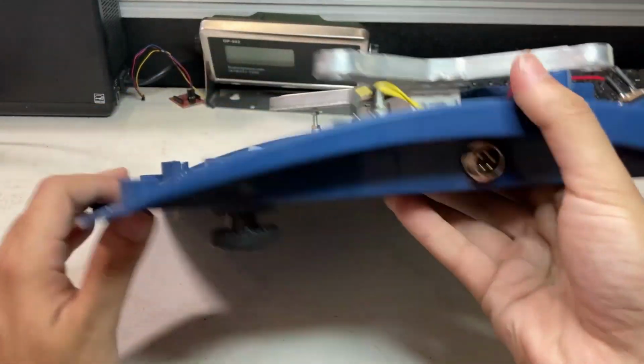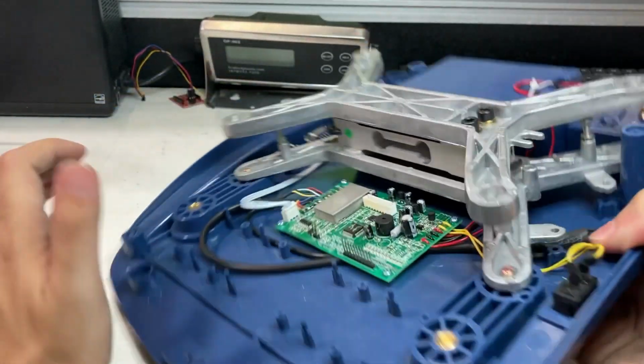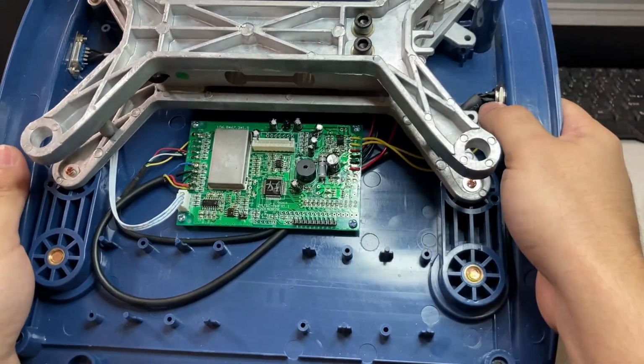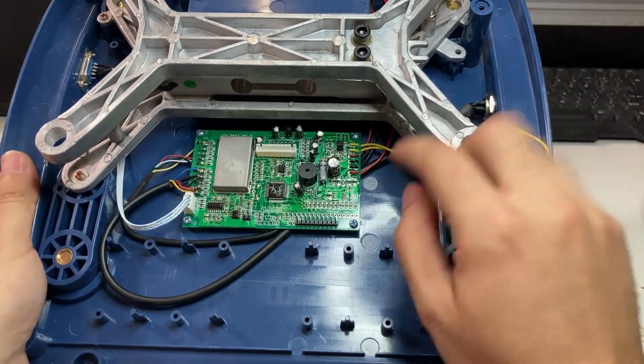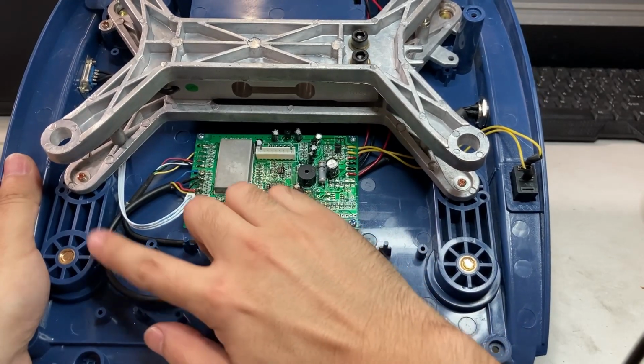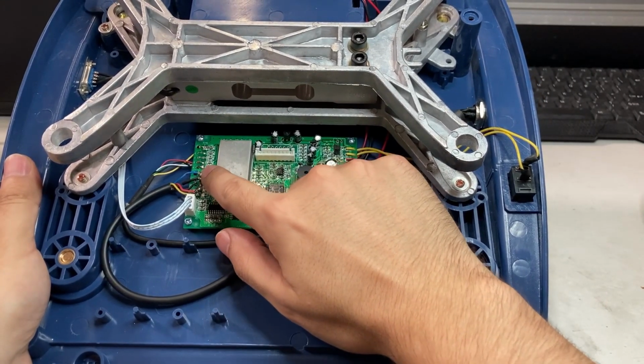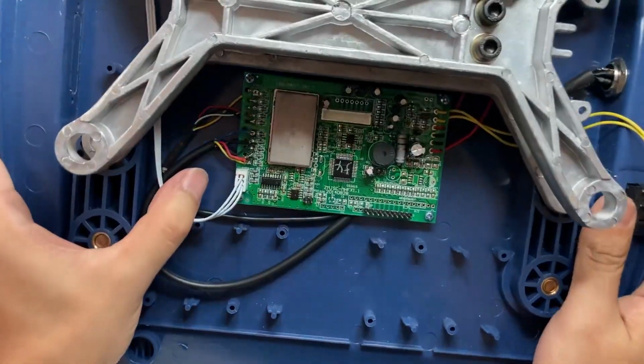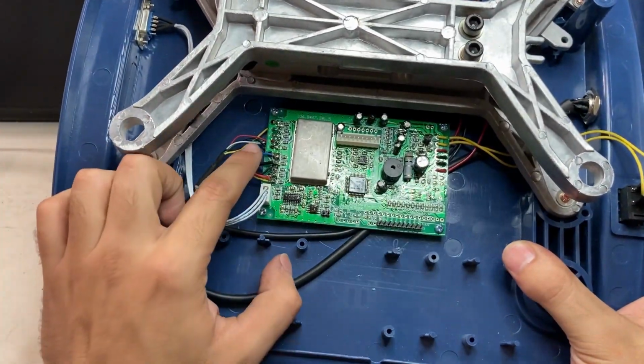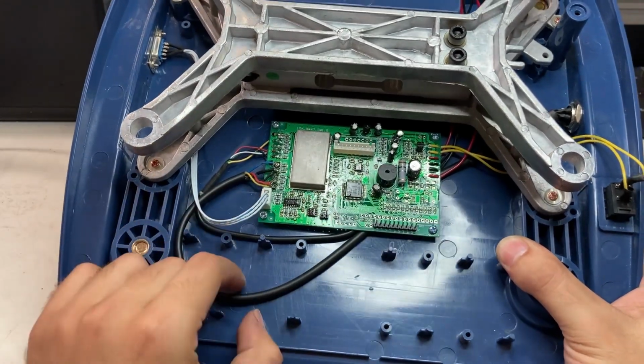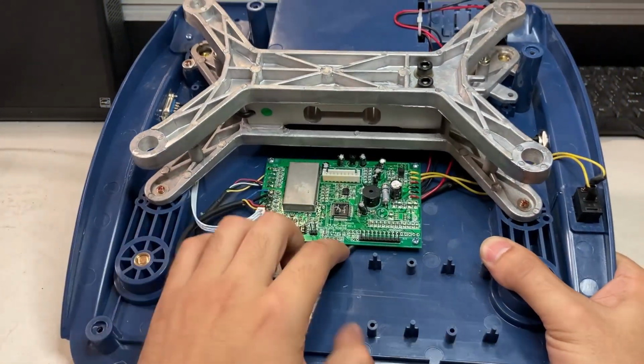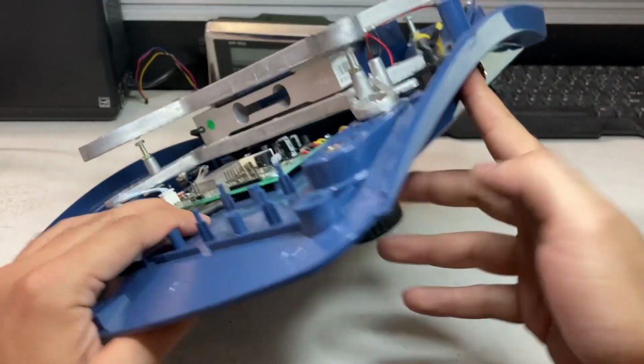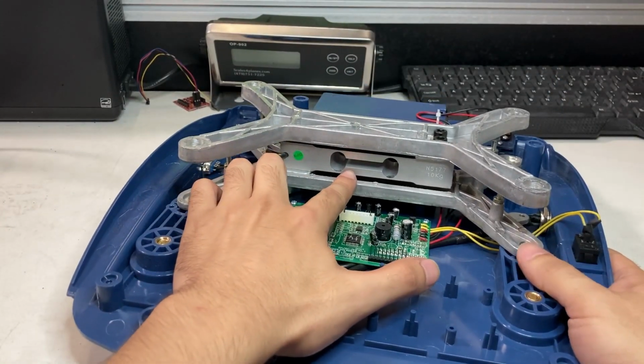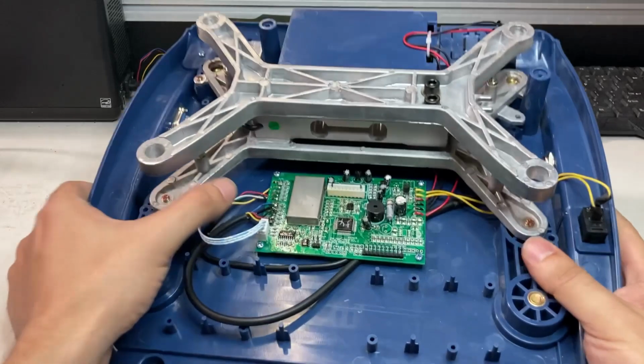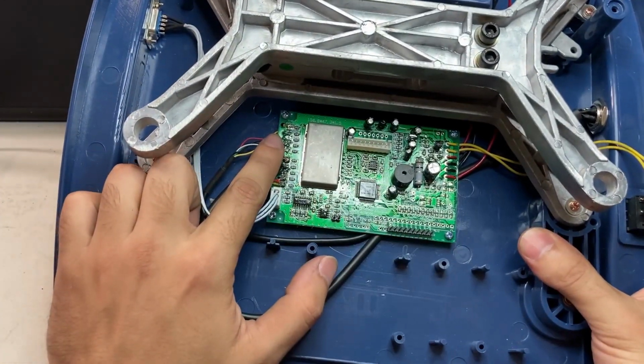What we're going to look at closely is the 5-pin, and you'll notice there's a cable here that goes downward, and it goes here. These solder points were mixed up and need to be fixed. For a closer look: you see these 5 are for this cable, which leads all the way to your 5-pin out here, and the other load cell is the one in the pan on top, the top one up here.